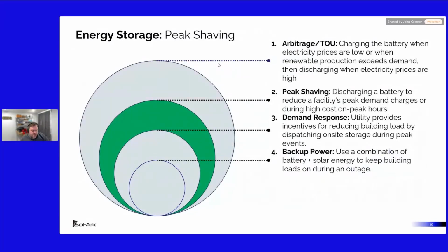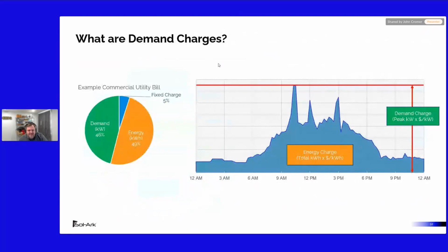There's another aspect called peak shaving, which used to be called demand response or demand management. Peak shaving is a better term: you have a demand charge on the electric bill, and you're shaving off just peak demand regardless of time of day. You can look at a demand charge bill, and if half the bill or more is demand charges, that's a pretty strong indicator it's a good project. Just look at a commercial bill, look at their demand charge line item, and get a sense of whether the project will work.